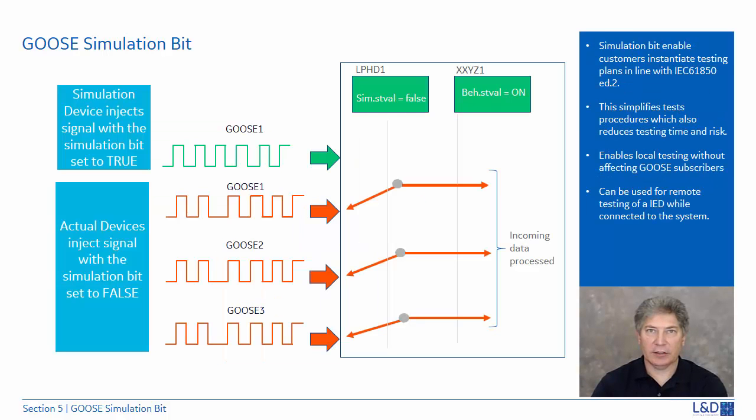Maintenance testing in cases such as IED maloperation requires it to be tested before putting it back in operation. In the typical case, this requires sending a testing crew to the substation to perform the testing, a time-consuming and very expensive process. The use of protection systems in a digital substation environment allows the testing to be performed remotely. However, the use of both sampled values and the GOOSE messages is required for the end-to-end testing.